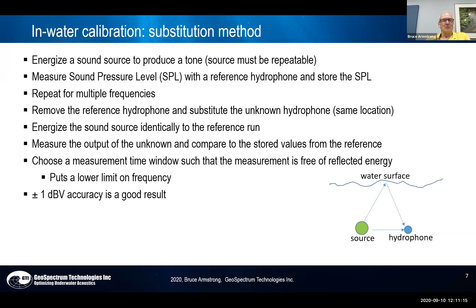One little wrinkle is that you want to measure the received sensitivity of the hydrophone without complications from reflected energy. So the depth of your calibration determines how low in frequency you can go. You know, there's a little transit time from the source to the receiver, and then there's a longer transit time from the source to the water surface and back down again. And the difference in those times is a maximum measurement window, so that determines the low frequency limit. And if you do a really good job, you can get plus or minus 1 dB accuracy. If you don't do a good job, you can be considerably worse than that.